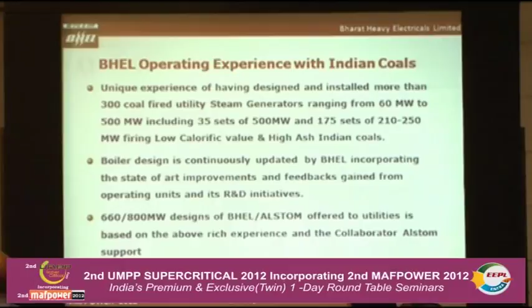Coals in other countries like US, Australia or South Africa are higher in calorific value and lower in ash. In our case, it is the opposite - ours is higher in ash and lower in calorific value. This calls for designing the milling system and all auxiliaries suitably for Indian coals. Also, Indian coals have a slightly higher erosion potential, therefore we design our boilers with conservatively lower gas velocities.